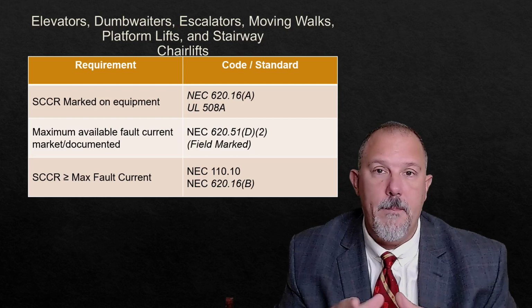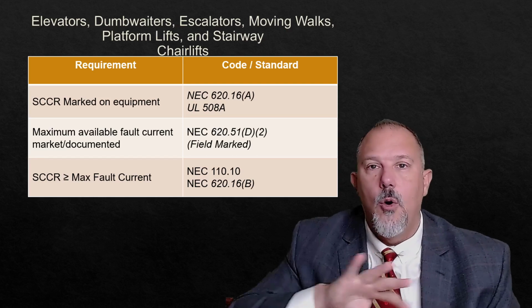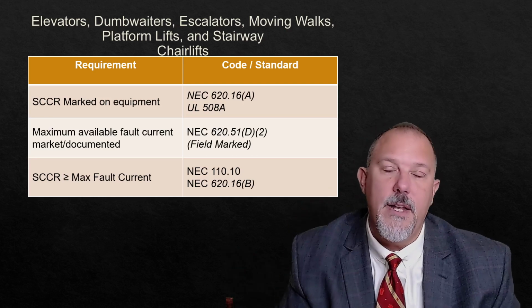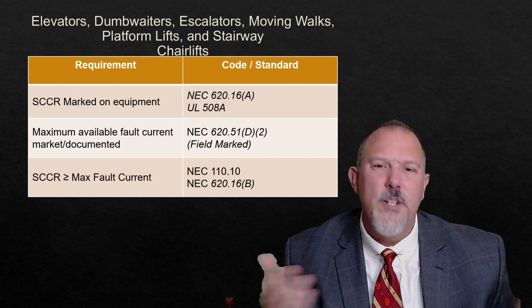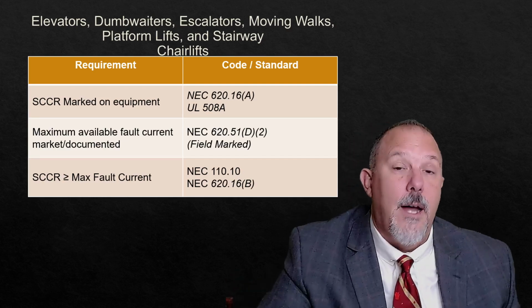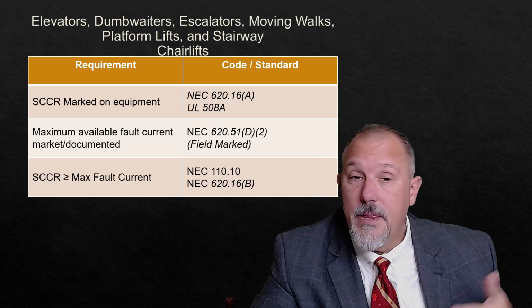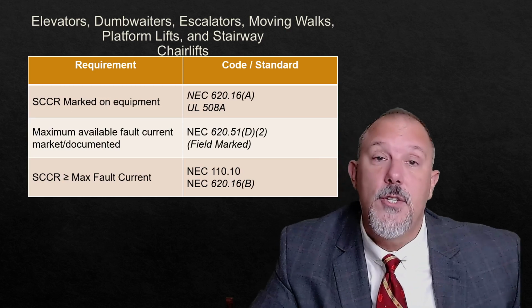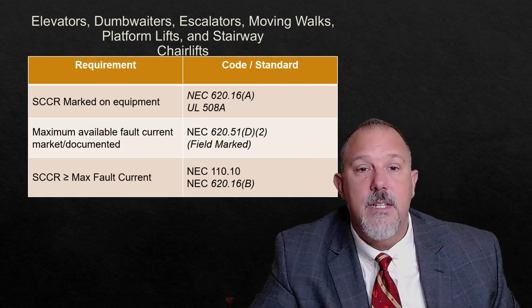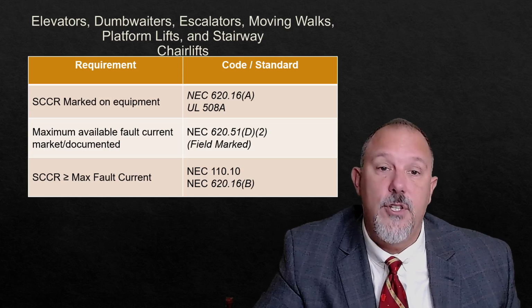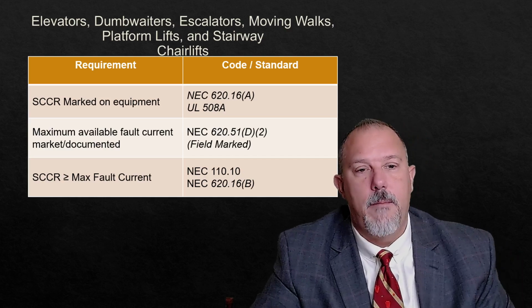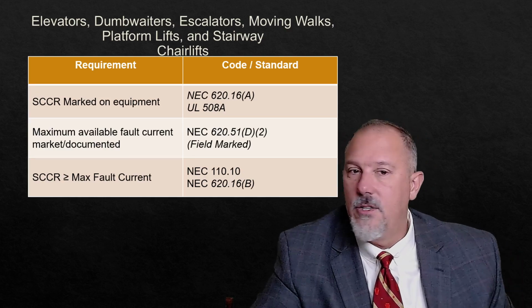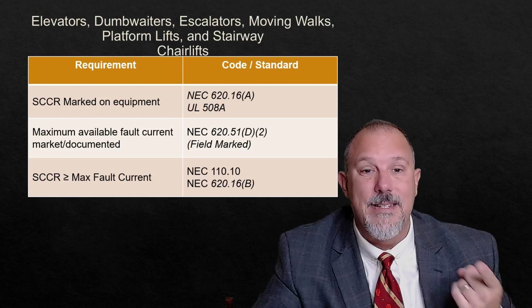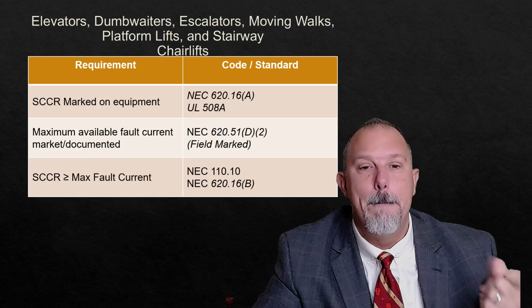Two different groups of people had two different philosophies. One code panel said, we want to mark it in the field. Another code panel said, we just want it documented. I wish everybody would be consistent, but it's okay, to each his own. And that's in 620.51D, as in David 2. And then SCCR greater than maximum fault current, 110.10 always applies, but it's also in 620.16B.